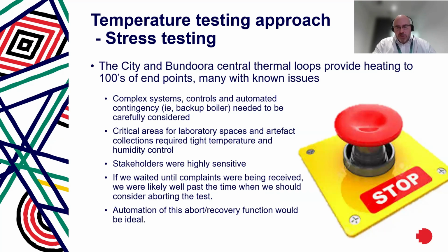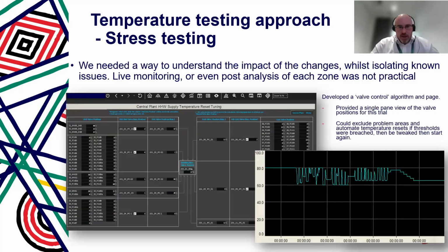We ended up introducing effectively an algorithm that sat in our BMS, and that looked at valve positions, and it was able to basically isolate where valves were opening to 100%, and that tells us where we've got large portions of valve opening to 100%, we've got capacity issues. Now this is important because we had to design and develop these pages. Most BMSs have the ability to understand where their valves are, but nobody really has pages pulled together to sort of look at that.